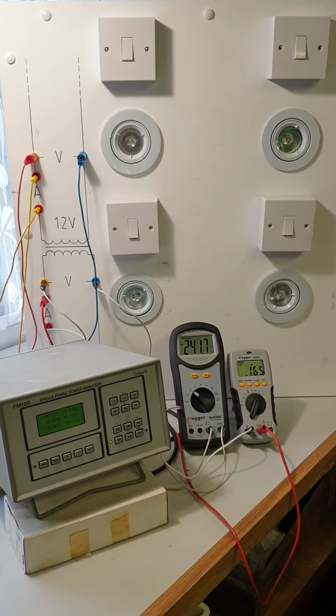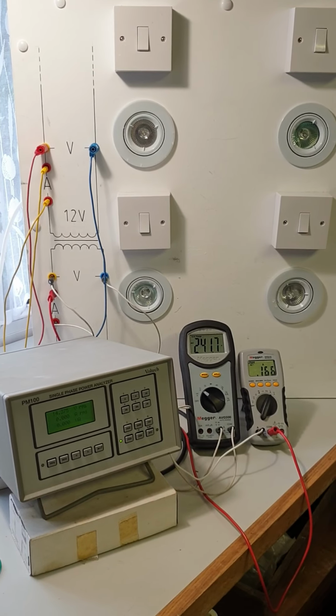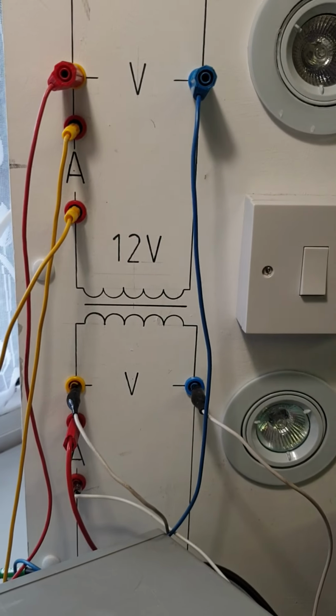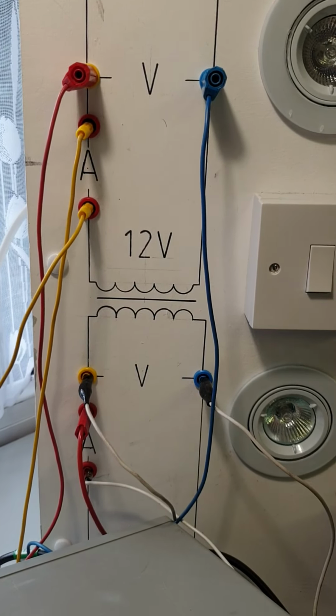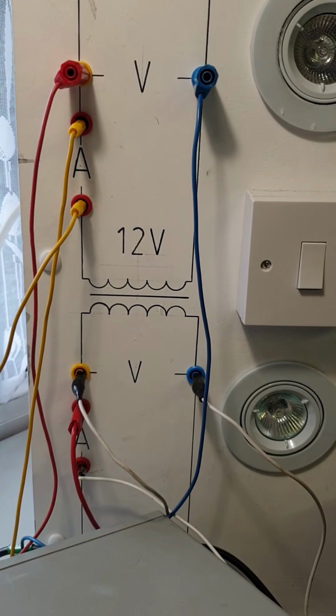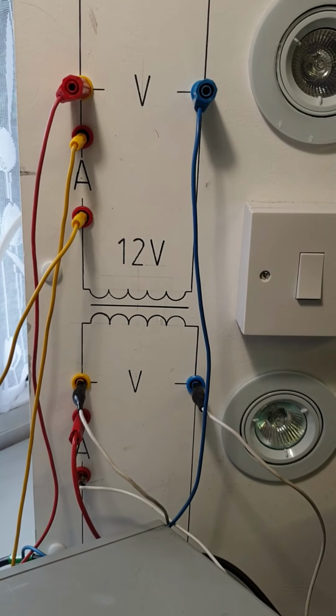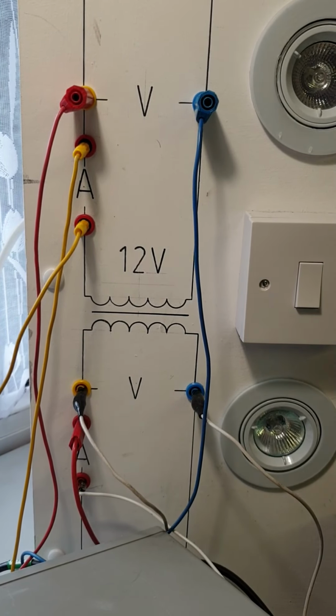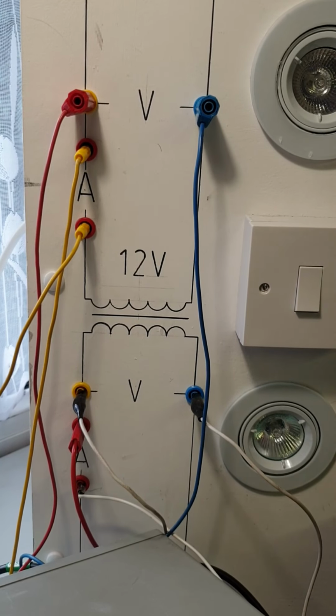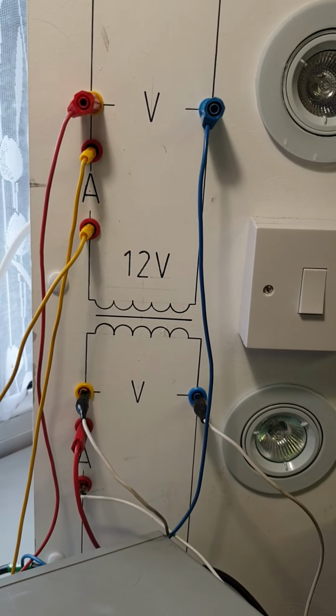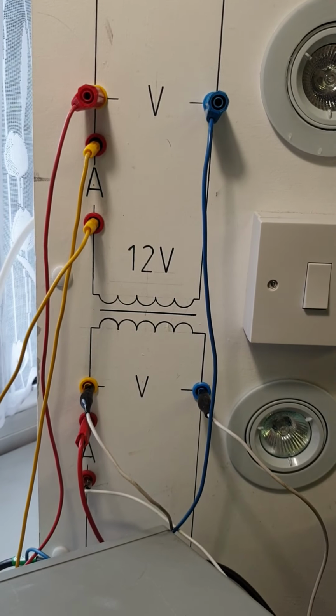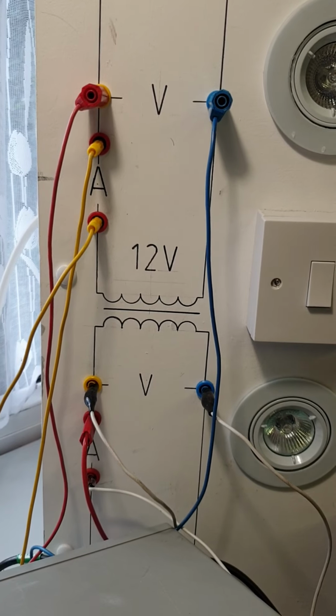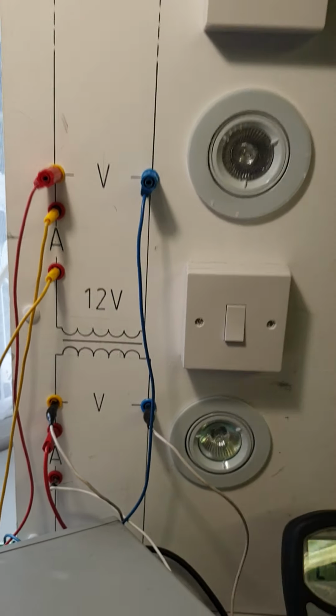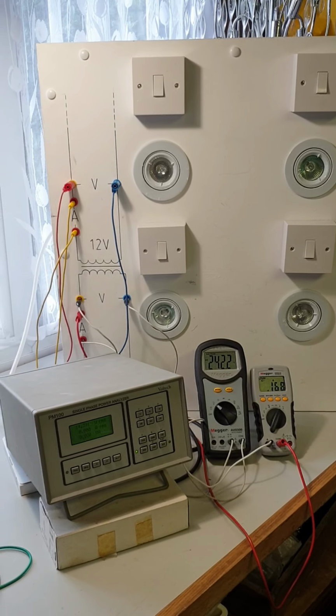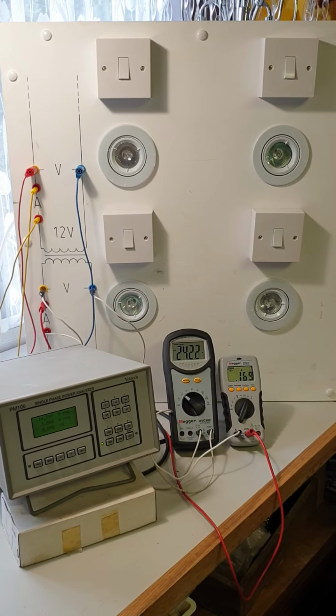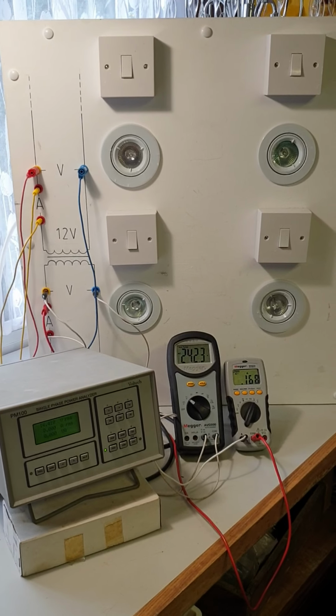We do a calculation which is called load regulation for a transformer. So the transformer, one of the measurements is what's the output voltage or secondary voltage under no load minus the output voltage under full load divided by the voltage under no load. When we calculate this, we come out with a percentage regulation, and for this example it should be somewhere in the region of 14-15%. Okay, we'll have a look at that. Okay, so again, that's all I need you to see on the practical. It's run into 7 minutes, which is a bit long. Okay, but we'll give it a bash.